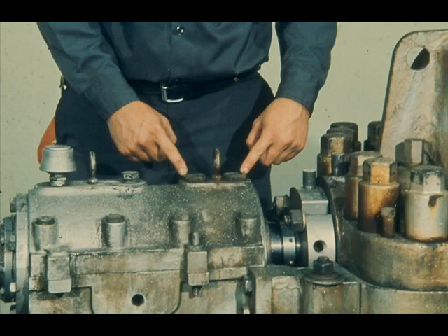Inspection plugs on the top half of the bearing housing permit filling the oil reservoir that provides lubricant to a sleeve bearing that is compartmented with the housing. By removing the plugs, the bearing oil rings may be observed.